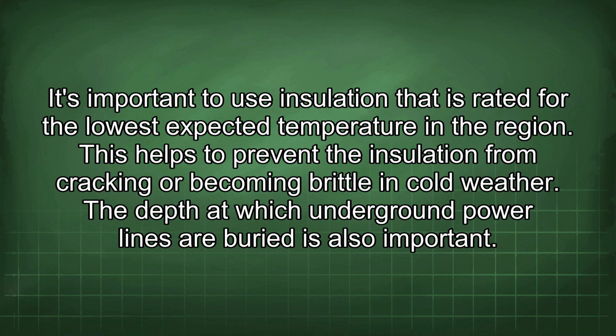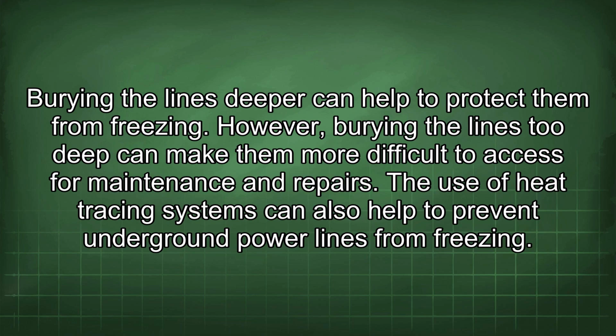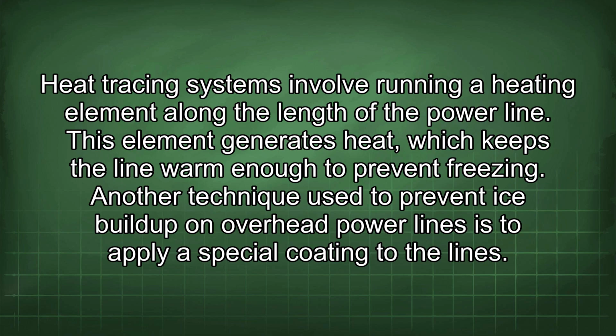The depth at which underground power lines are buried is also important. Burying the lines deeper can help to protect them from freezing. However, burying the lines too deep can make them more difficult to access for maintenance and repairs. The use of heat tracing systems can also help to prevent underground power lines from freezing. Heat tracing systems involve running a heating element along the length of the power line. This element generates heat, which keeps the line warm enough to prevent freezing.